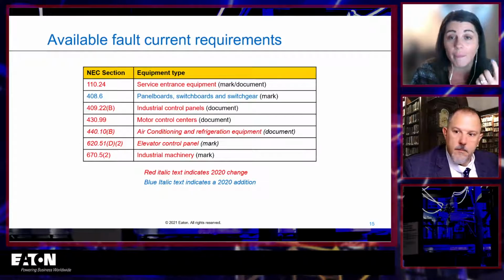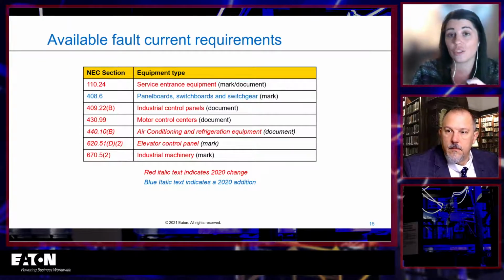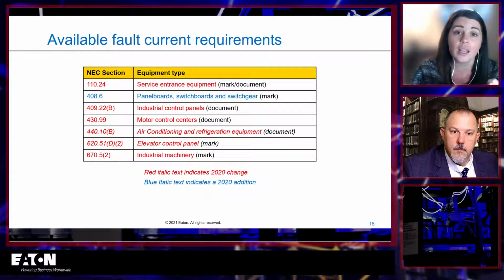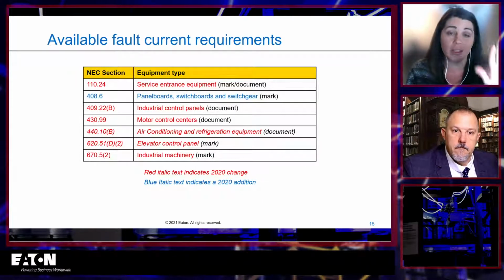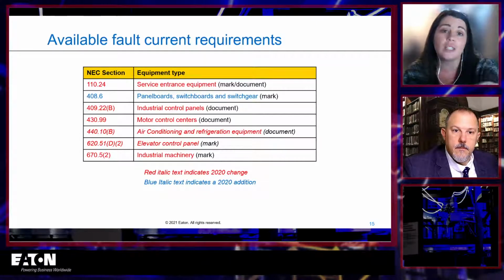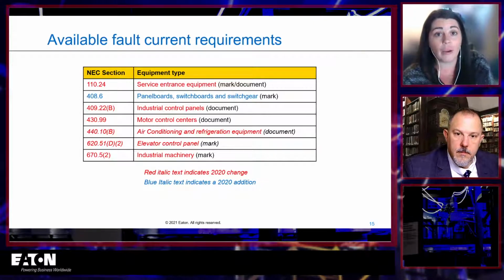And so it might be documentation, so just proof that you've done the calculation and you know what the available fault current is, or it might actually be a marking requirement, so a field marking. You've got to actually put a sticker on your piece of equipment that says the available fault current here is X. So you can see all of those different types of equipment, and we'll go through each of these individually, so I'm not going to read them out now.